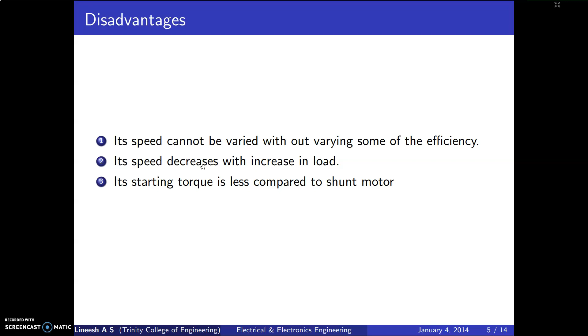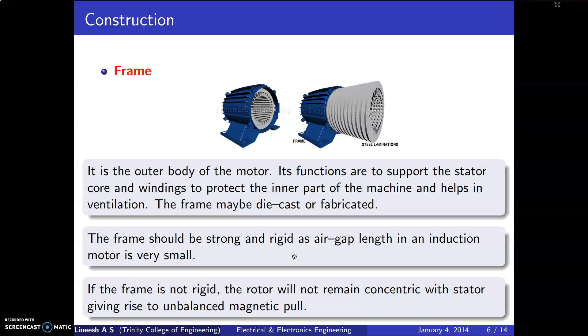Next is the construction of the induction motor. First of all, the outer covering of the machine is called the frame of the motor. The frame is the outer body of the motor. Its functions are to support the stator core and winding, to protect the inner part of the machine and to help in ventilation. These vanes will help with ventilation. The frame may be die cast or fabricated. The frame should be strong and rigid as the air gap length in an induction motor is very small. If the frame is not rigid, the rotor will not remain concentric with the stator, giving rise to unbalanced magnetic pull.